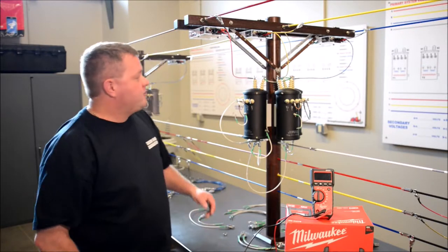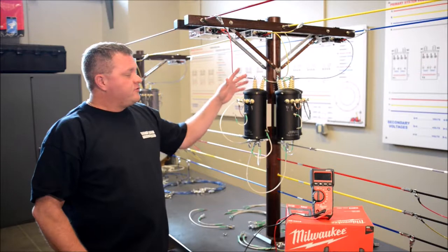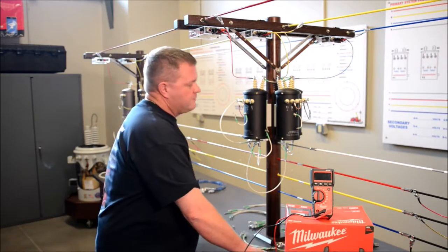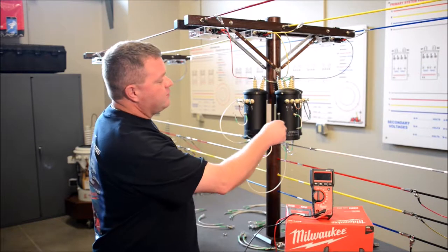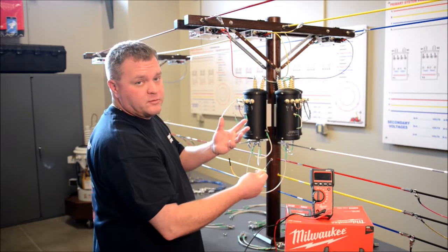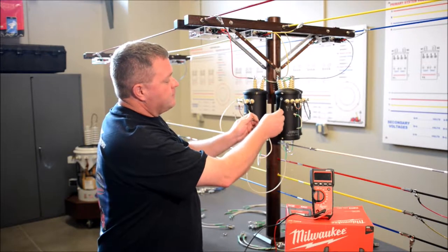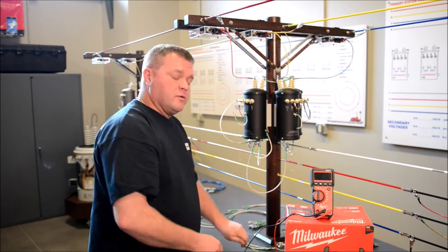So what we actually have here is a Y high side and a Delta low side. You'll notice this open point right here between this X1 and X4, or if it's a 3 bushing it'd be X1 to X3. But before we make this connection we need to test this.